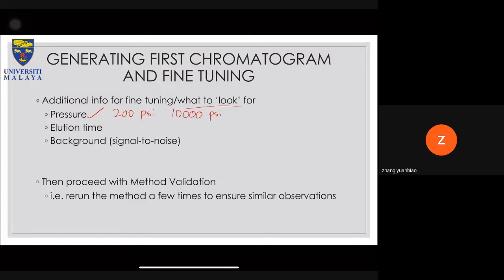Some information that you need to look for during your fine tuning is the pressure, to make sure that the pressure is good, and the most important thing is constant. So regardless of the range of the pressure, as long as it's constant, normally it is okay. Normally, not always, normally. You also need to consider the elution time. You don't want the elution time to be too long, 1 hour, 2 hours, unless it's necessary. So you want to reduce the time so that you can inject and run more samples, then your company will gain more money per sample.